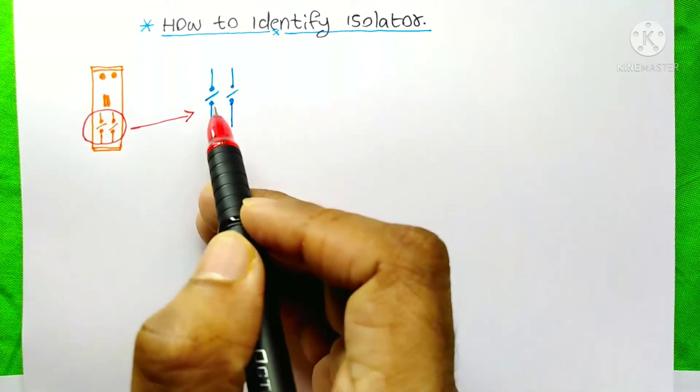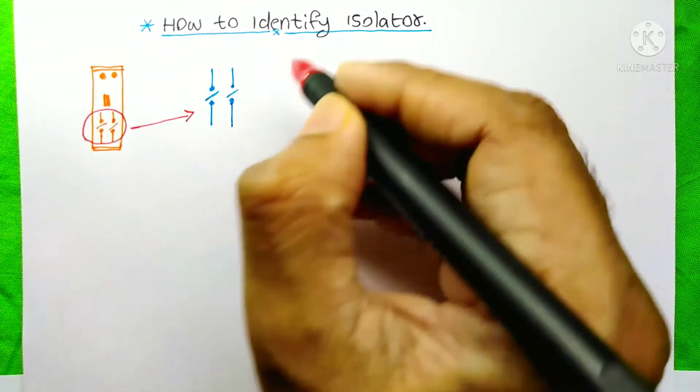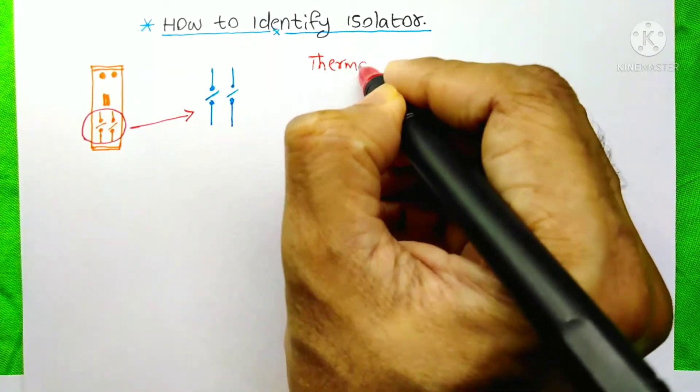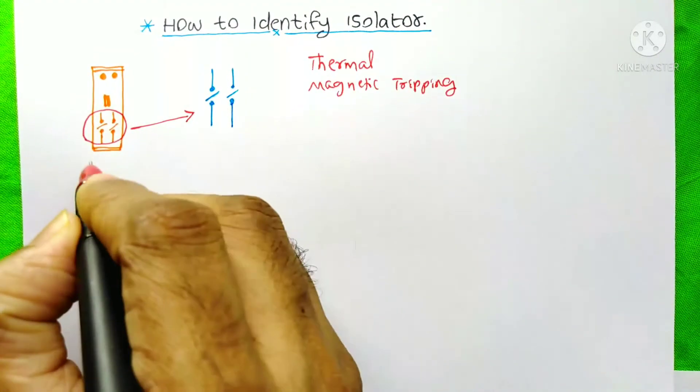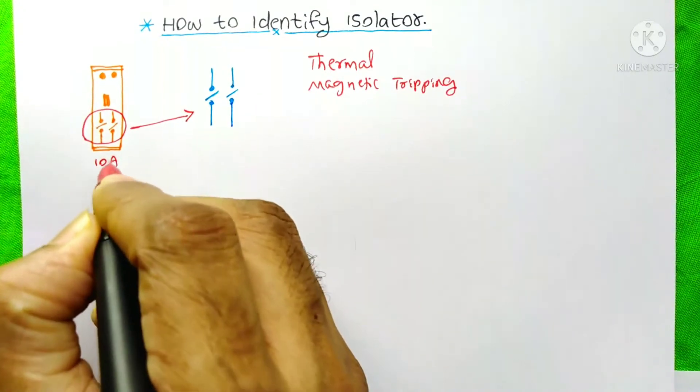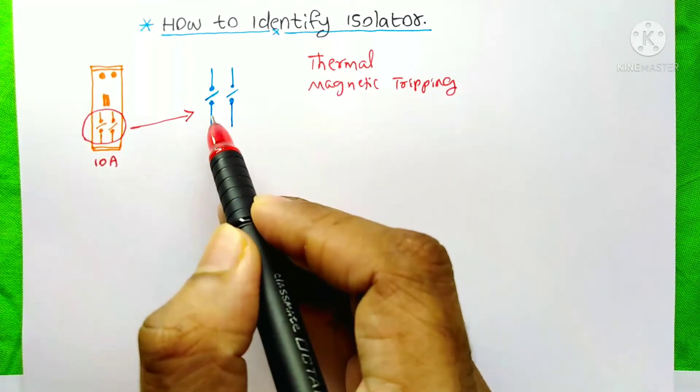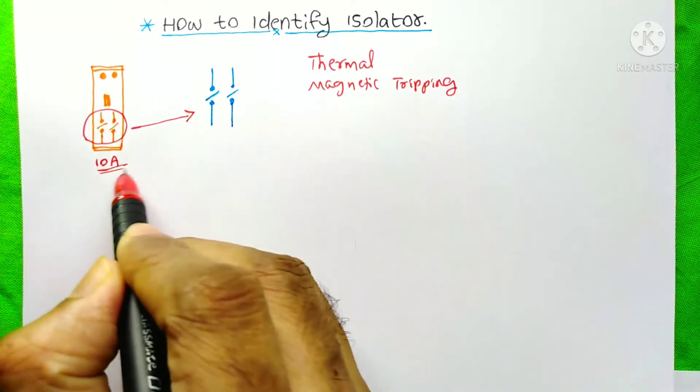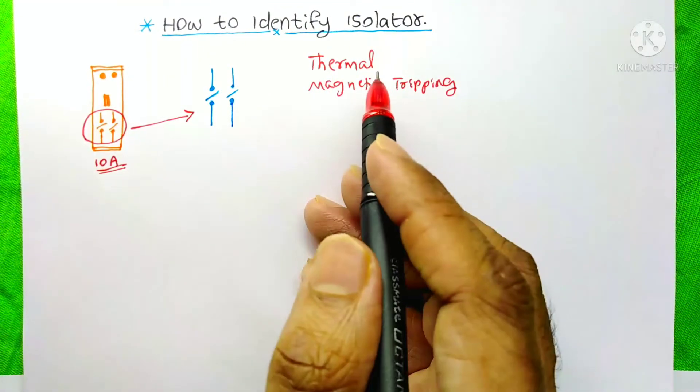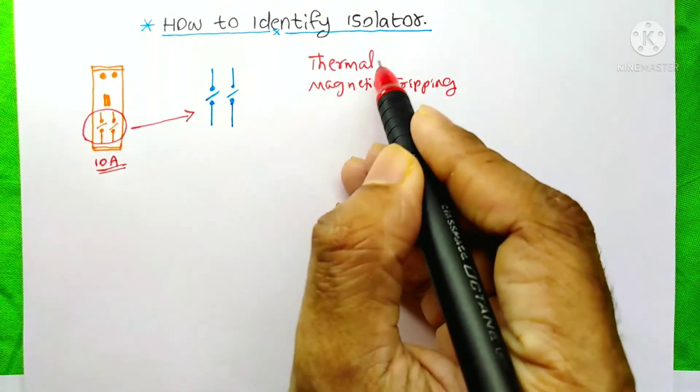These are only the normal switches. It will not give you any thermal and magnetic tripping functions. Suppose this isolator is of 10A, then if the current on this circuit is more than this 10A, then this isolator can't give you the thermal protection.